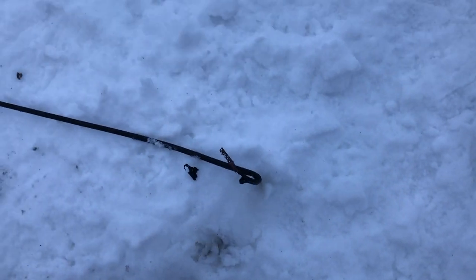Here you're looking at a gutter with some burnt cable in it, and these homeowners vacation through the winter time, so it would have been a pretty bad situation if they were out of town. Plugged into a thermostat, but there's no switch on the thermostat, otherwise I could turn it off.